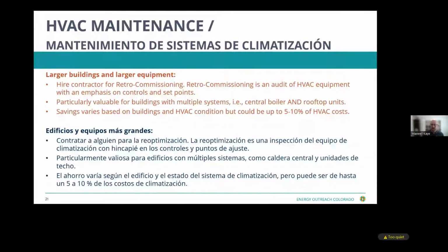They'll assess what the current state is and how it was designed, and bring it back to hopefully its original design state based on manufacturer's recommendations. This is very variable in savings because it really depends on what the maintenance history of that equipment was. We show an average of 5 to 10% savings here, but for some buildings we've seen much higher savings, even where we've caught buildings that are simultaneously cooling and heating at the same time because the controls have no longer been communicating with each other. Next slide.